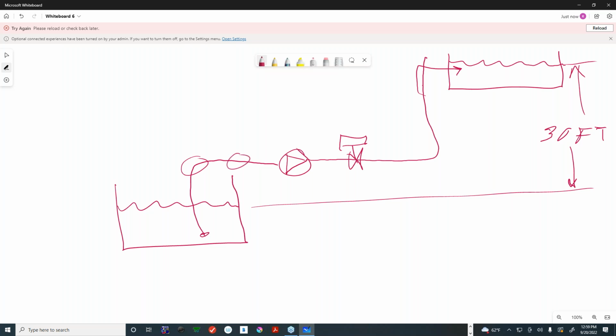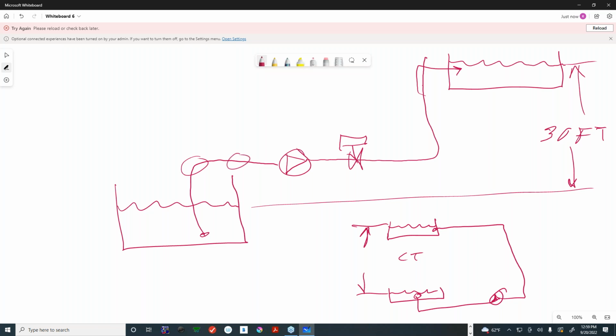And so Heidi asked, what about static head of cooling tower above pump level? So that's not added in at all then, right? Say what's the question? What about static head of cooling tower above pump level? No, it's only the difference in the cooling tower height, because even though we think of a cooling tower, it's actually two tanks. One is up here. This is an oversimplified cooling tower. And the other one is down here. So if we're pumping from the lower tank to the upper tank, there's a pump, then we take the water level difference between these two for our static.